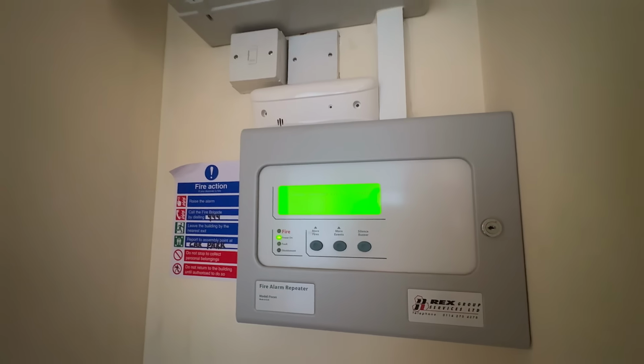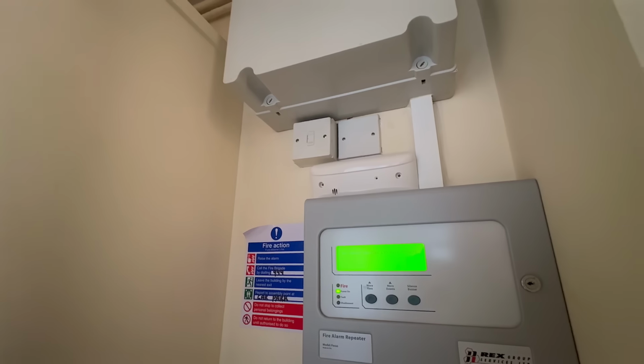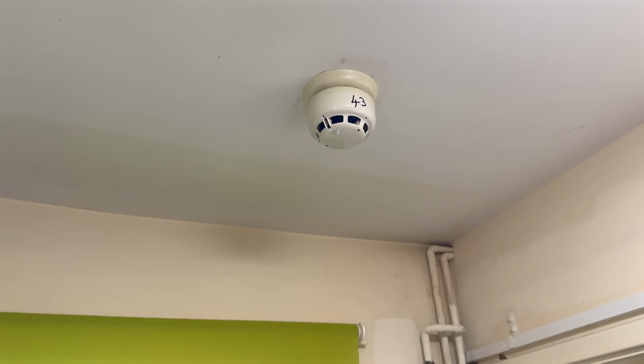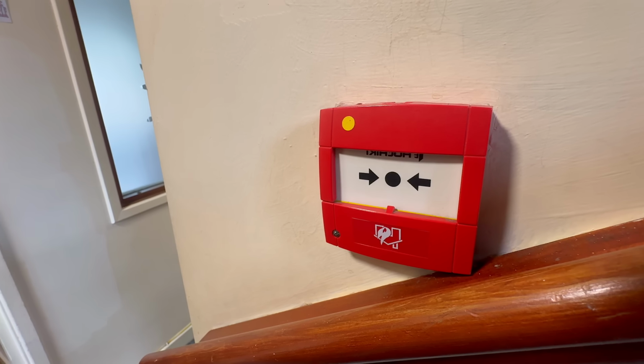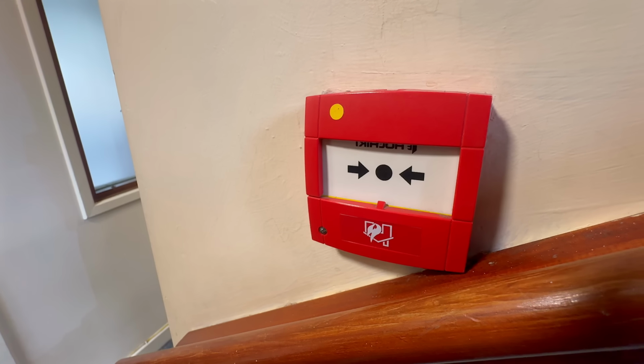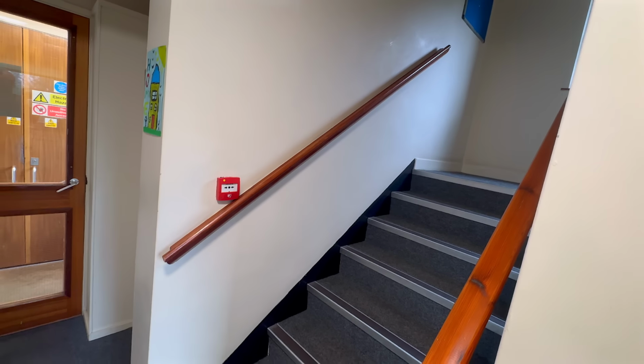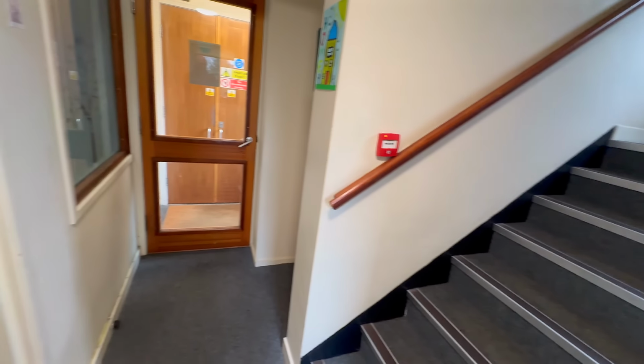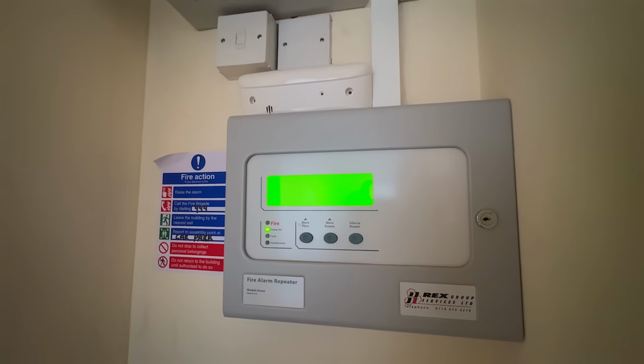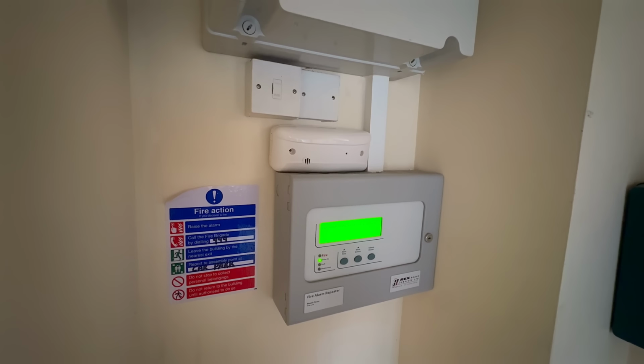It moves to a grade A system with LD2 coverage and detector siting aligned with BS 5839-1 category L2 approach. It reflects the fact that the communal areas are shared escape routes and fall under different fire safety duties. A grade A system has a centrally controlled panel and is designed to protect those shared spaces properly.